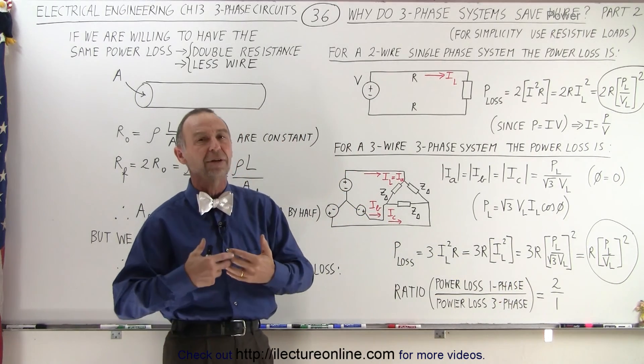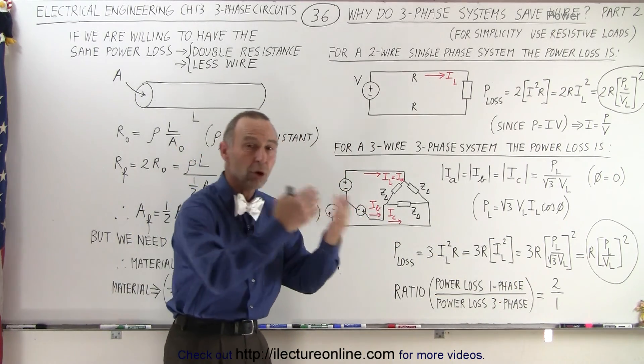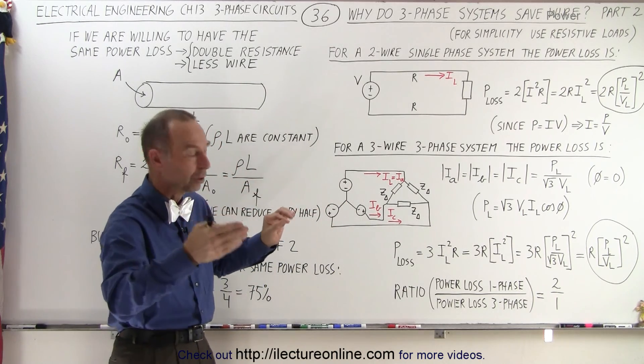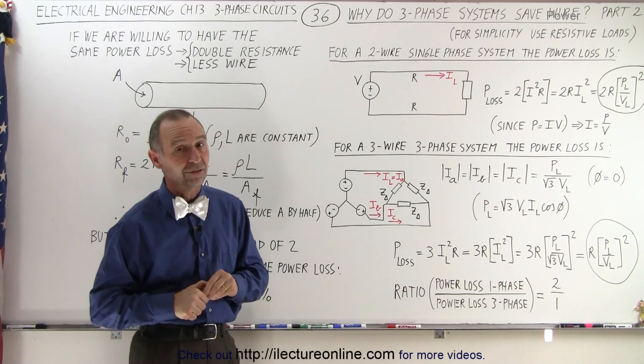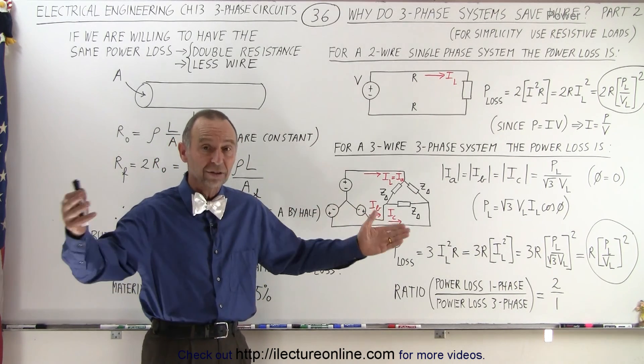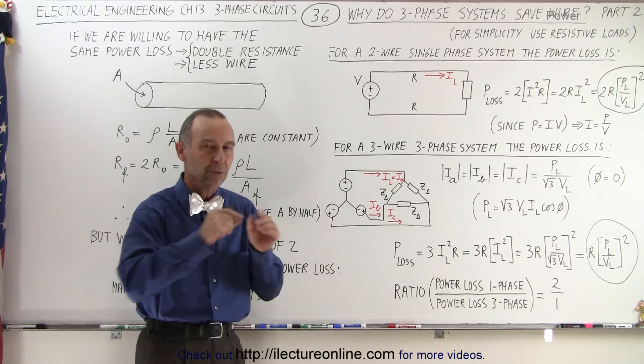We lost twice as much power delivering the same amount of power to the load. We lost twice as much power on the wiring to the load in a one-phase system versus a three-phase system. So that's a tremendous power savings, especially if that wiring is very long.